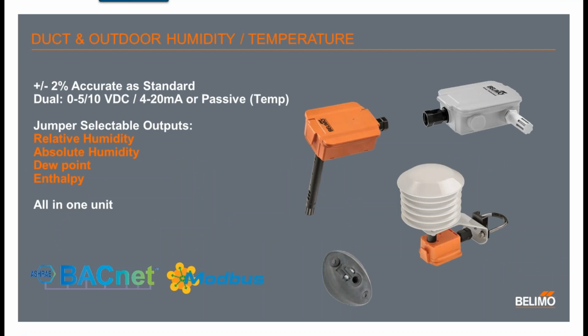You can select 2 voltage outputs or 2 4 to 20 milliamp outputs for temperature and humidity, or you can have passive for temperature only. The humidity sensors come as standard with relative humidity output, but in the same device you can jumper select that to read absolute humidity, dew point, and also enthalpy, all in the one device. Selected models are also available with BACnet MSTP communicating and also Modbus RTU.